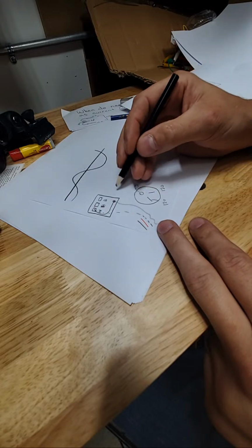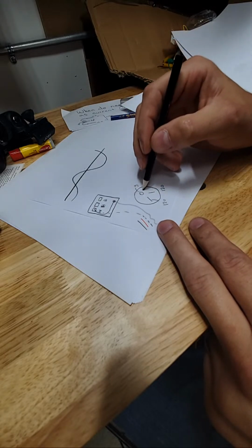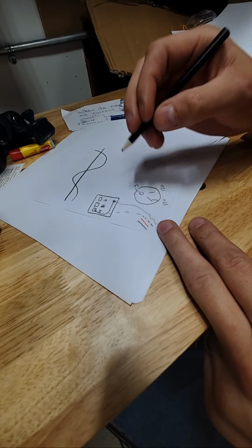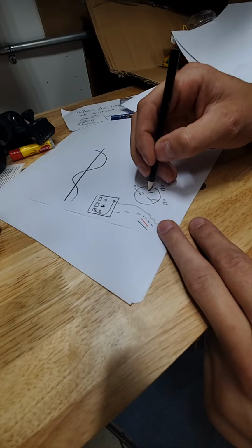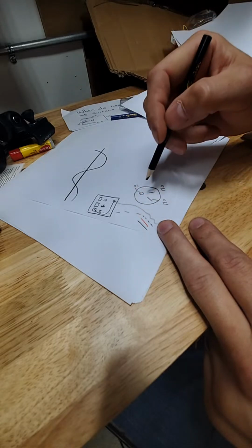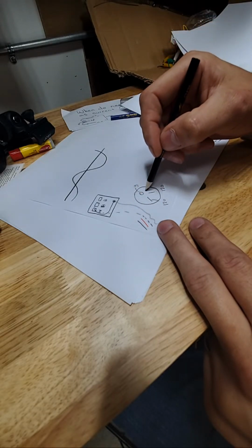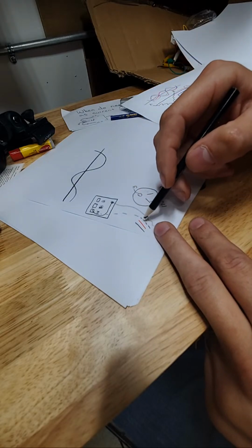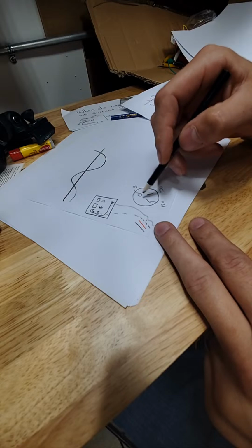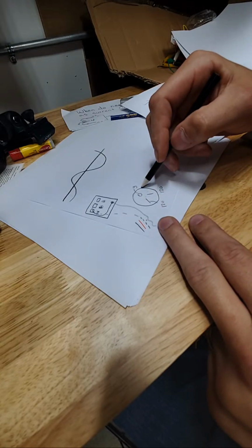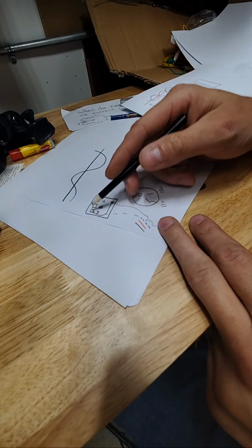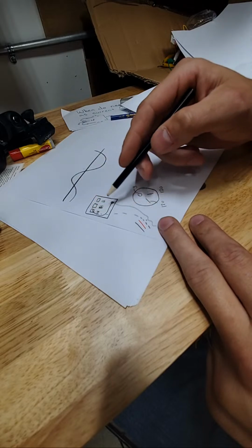As long as they don't touch the wiring and they don't change the plug out, it's fine to stay existing. But the second they change this plug out, we know the wire coming from the panel does not have a neutral. And that's a false sense of security, because someone's going to plug in a 4-wire cord into this 4-wire receptacle, but there's only 3 wires feeding this plug as far as the building goes. And then you haven't jumpered your ground and neutral together. And you got a problem.